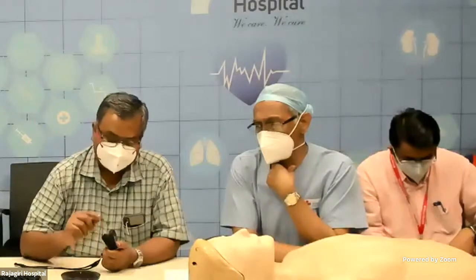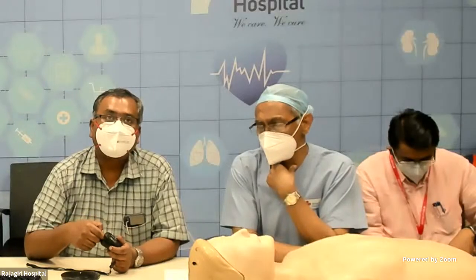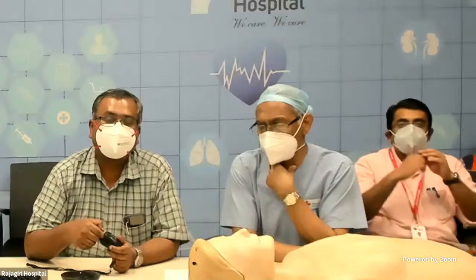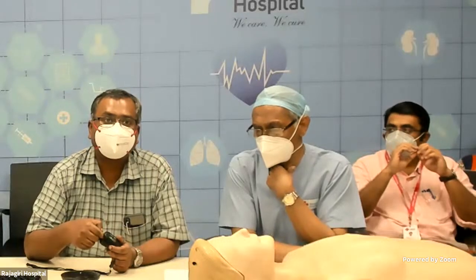There can be problems when you apply it in the wrong way. Suppose you apply it in a tangential way. If the finger is not inserted properly, the light rays cannot pass perpendicularly through the body tissue, and the reading can be wrong. If the patient is wearing nail polish of certain colors, like blue, green, black, and colors like that, there can be an erroneous reading. Fortunately, red nail polish is not found to cause much problem with the reading. Now, how do you know whether the reading is inappropriate or not? You need to have proper clinical judgment.